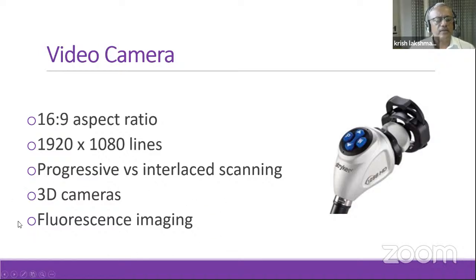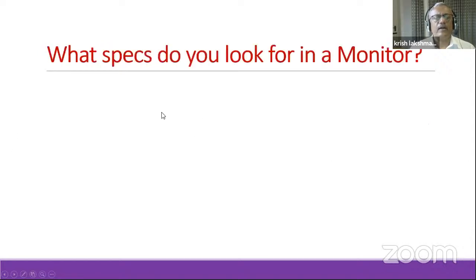These are the newer techniques available. But it's important for you to know that nowadays we go with a high definition three-chip camera as a standard for laparoscopy. You must understand one basic thing in laparoscopy - your telescope must be an HD telescope. If you want an HD image, you can't use a telescope with less resolution, and you can't use one with less resolution with a fancy camera. It won't read it because the telescope doesn't read anything good enough. So you must have a good HD telescope, a good HD camera, and the monitor has to match it as well.